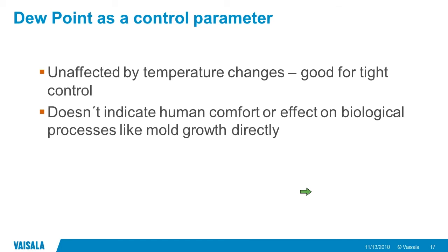So as a control parameter, if you're trying to do a very tight simultaneous control of both humidity and temperature, dew point control is actually a pretty good idea.